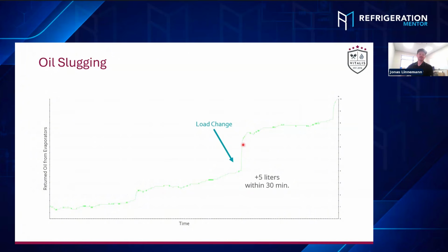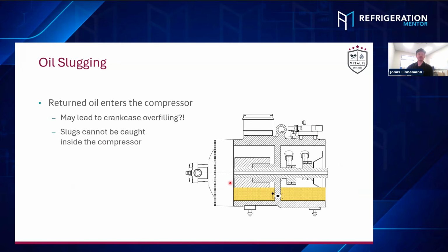So this 5 liters within 30 minutes, that's definitely too much for a compressor, right? So having a look on the cut model of the compressor again, the suction with the oil travels in the suction side here on the motor side. And you would think, okay, the idea is that the oil settles down and flows back into the crankcase and does its job for lubrication. But there are two things. If you get too much oil back, it can't bypass into the crankcase through these little tiny check valves quick enough. So it's remaining in the motor part.